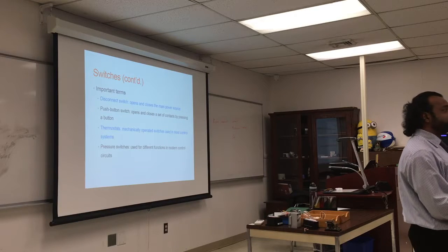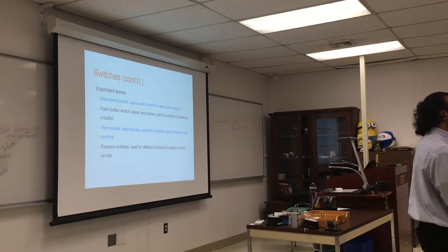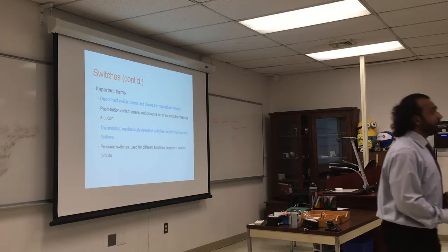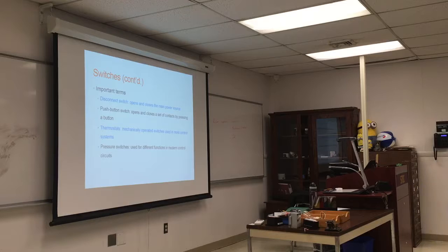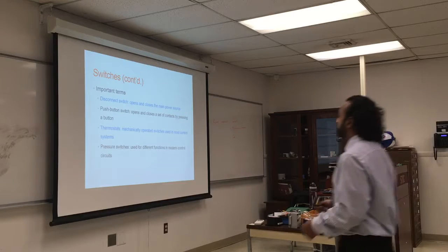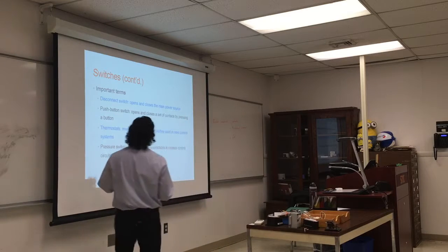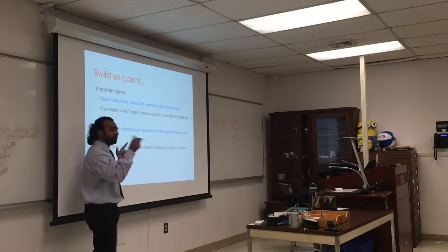By NEC, we have to have a disconnect switch near every piece of equipment. If the equipment is outside, you'll have the switch outside. If you install a mini split and the unit is outside, they have to have a disconnect switch next to it. Why? If it catches on fire or is making a loud noise, you want to be near it and disconnect, instead of running all the way to the basement and trying to find it. It should be visible. Push button switches open and close a set of contacts by pressing a button once.